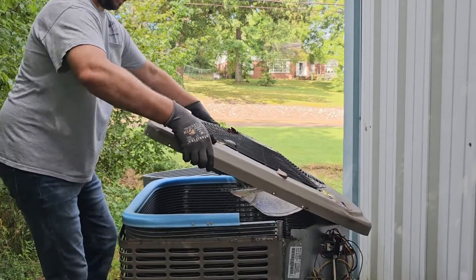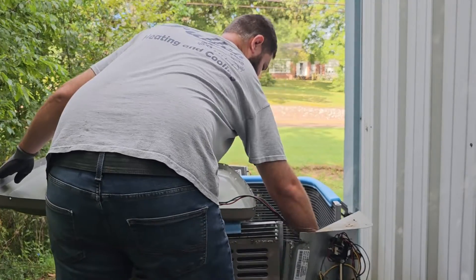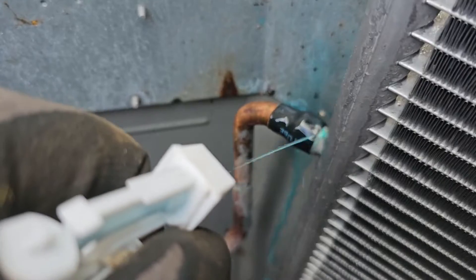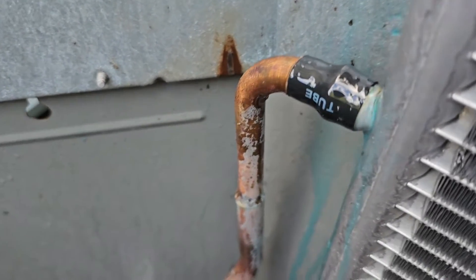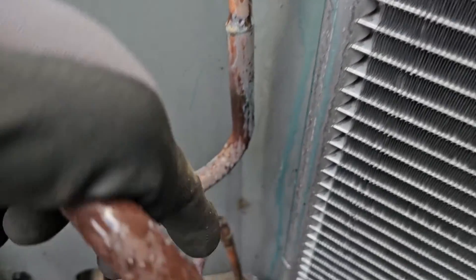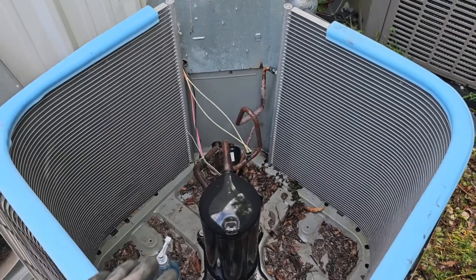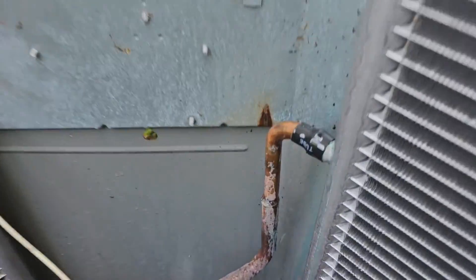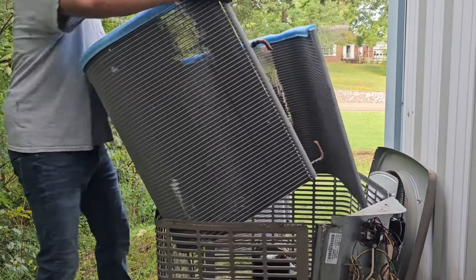It's super light. Got the top off. It's leaking right here — you see that? This is less than a year old. The connections that have to be brazed are this connection and this connection. I was not even going to try to repair this because it is less than a year old and still under warranty. It was replaced less than a year ago because it was leaking. I'm not going to repair it — I'm going to replace it. I'm going to get this old coil out of here and cut the old connections.